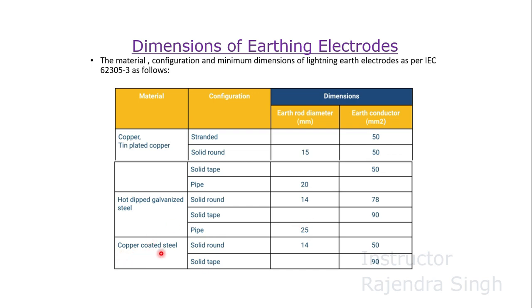For copper coated steel: if the configuration is solid round, the earth rod diameter would be 14 mm and the earth conductor would be 50 square mm. For solid tape configuration, it would be 90 square mm for the earth conductor dimension.